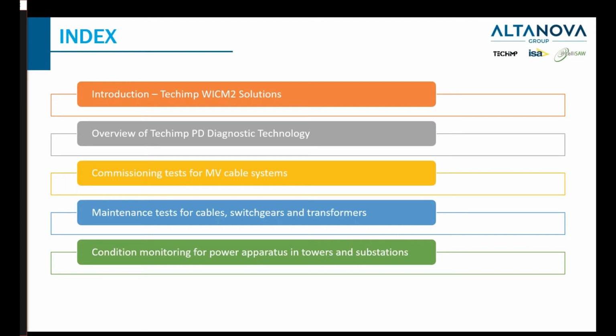The first part is the commissioning test, mainly for the medium voltage cable systems. The second part is the maintenance test. Once the wind farms are installed, we need to ensure the reliability of all the assets, like cables, switchgears, and transformers. We need to ensure their performance is good, and they do not experience premature failure. So that's in the maintenance test. And condition monitoring is the extension of the maintenance test. So instead of doing the test like once a year or once every other year, condition monitoring will keep an eye on the equipment at all times and raise the alarm or send an alert to the operators once there's any indication of aging or degradation. So those are the main contents in this webinar.